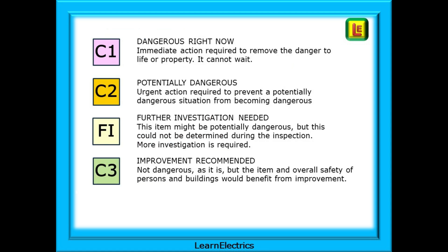What do the codes mean? C1 is dangerous right now — immediate action is required to remove the danger to life or property. It cannot wait. C2 is classed as potentially dangerous — urgent action is required to prevent a potentially dangerous situation from becoming dangerous. FI means that further investigation is needed; this item might be potentially dangerous, but this could not be determined during the inspection. And C3 is for improvement recommended — it's not dangerous as it is, but the item and overall safety of persons and buildings would benefit from improvement.